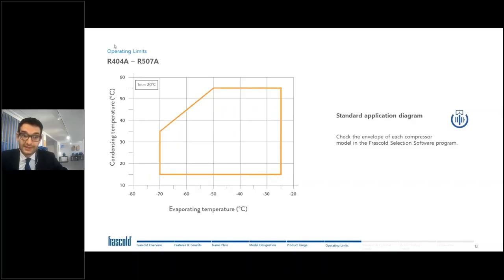You will find in the software also the application envelope with 448 down to -70, because as I mentioned at the beginning, the F-gas regulation does not apply for cell temperatures below -50. So we can say evaporators between -55 and lower are not in F-gas. So if you find it available, in this area you can use 448, and you can use this refrigerant also in the future, in the next years. I repeat, the problem is whether it will be available for the next years.